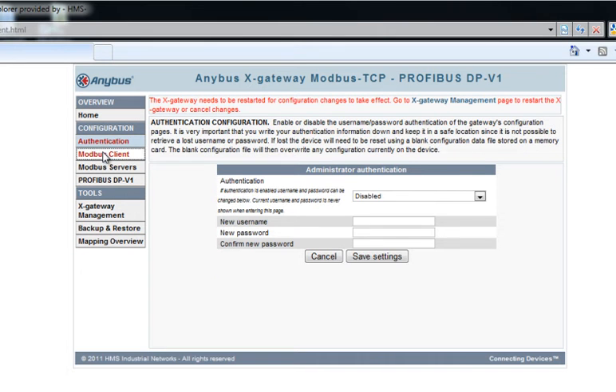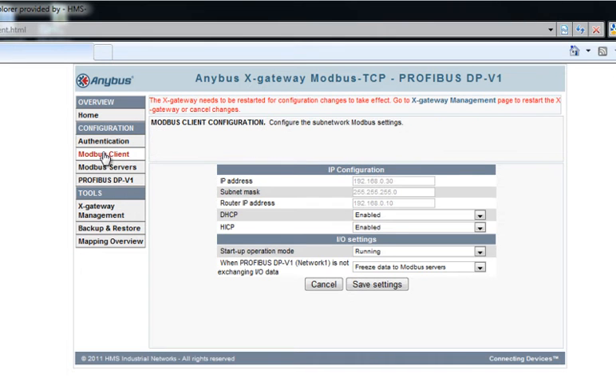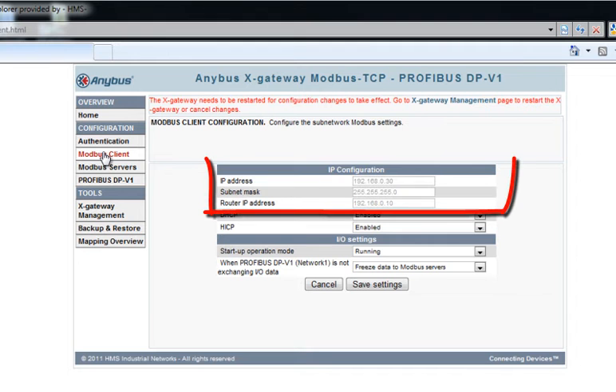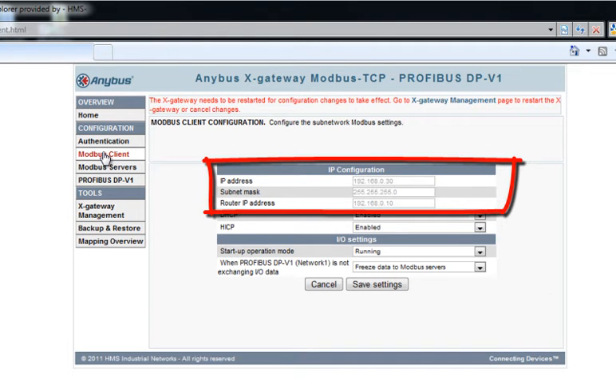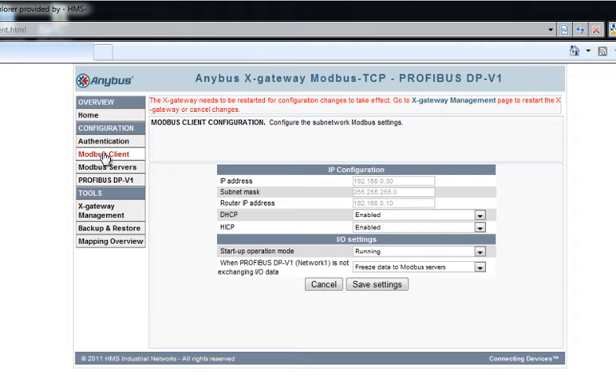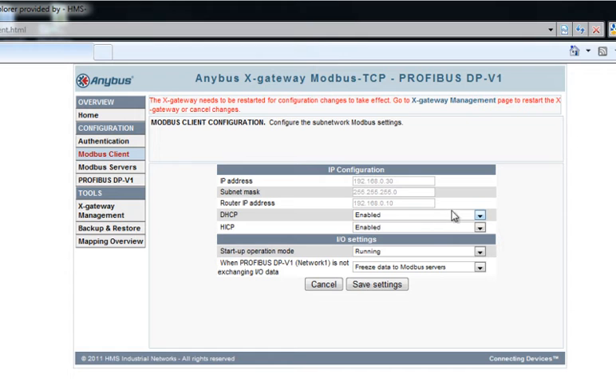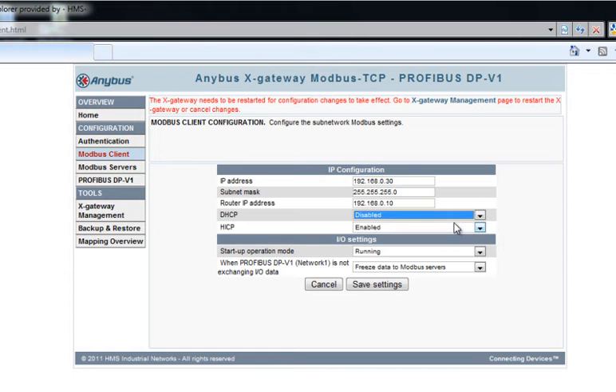In Modbus Client, I set up how the Modbus Client should perform. In Modbus terms, the client is the master. Here, I can set up IP address, subnet mask, and router IP address. In this case, this is all set automatically by a DHCP server on the Modbus TCP network. With a DHCP server, the IP configuration is dynamic, so to make the numbers permanent, you need to disable DHCP and specify the numbers.